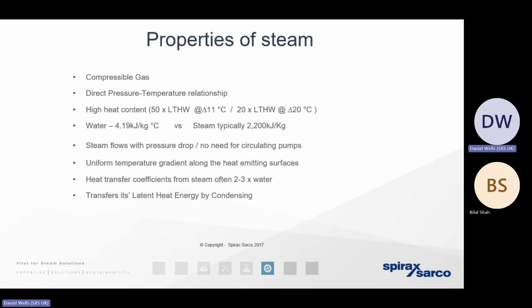I think one of the critical fundamentals that we need to get across when we're talking about steam systems is that phase change. When steam gives up its heat energy, it condenses, it changes state from a gas to a liquid. That liquid condensate is going to exist at exactly the same temperature. So it's critically important that we don't fall into the trap of confusing the point of energy with temperature. They're 2 completely different issues. That condensate will exist at the same temperature as the steam, but because it's got far, far less energy contained within it, it needs to be considered as a byproduct whenever it's in the pipework or in the heat exchanger itself.